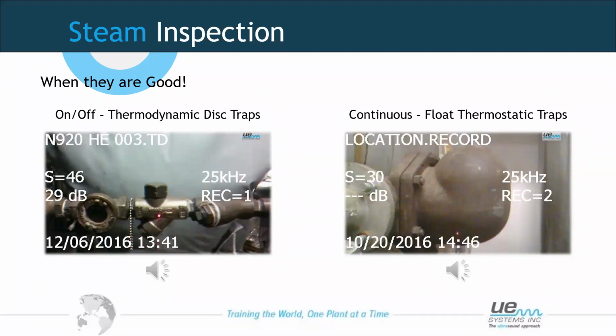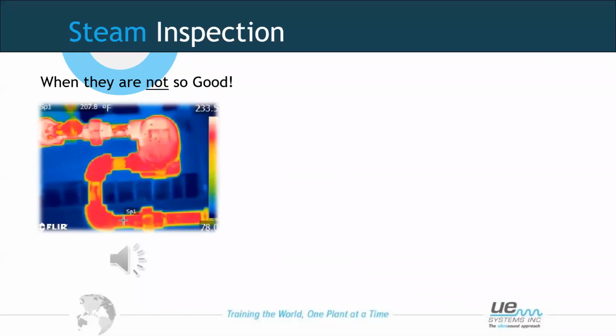So that means that if it's failed in an open position, we've got a continuous flow of steam at high pressure, which means we would expect to hear a large amount of turbulence. So when they're not so good, it would sound something like this. As you can hear from that sound, it is just straight through turbulence. There is no fluctuations in the sound.